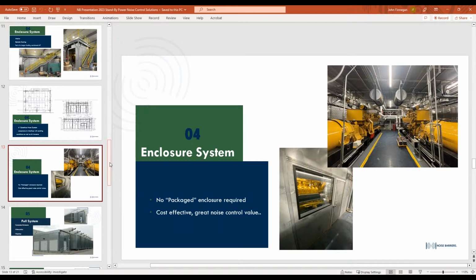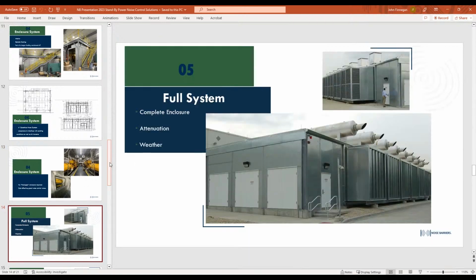So that's what I call just a basic enclosure system. Then you get into the full systems, and this is where noise barriers take on the inlet, the exhaust, the pressure drop issues I talked about, the attenuation needed. We do not do mufflers, so the muffler has to be rated to the level of my enclosure, or you're kind of defeating the purpose. But we work with the engineers and the designers, and then ultimately the engine supplier, with what muffler they're supplying, so that we're not attenuating less than the muffler or more than the muffler.